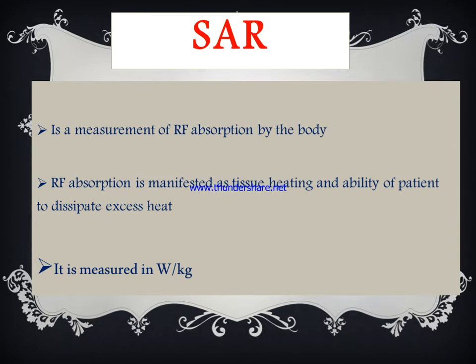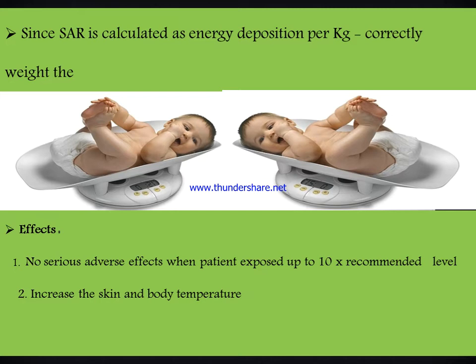SAR means specific absorption rate. SAR is the measurement of RF absorption by the body. RF absorption is manifested as tissue heating and the ability of the patient to dissipate excess heat. SAR value is measured in watt per kg. Since SAR is calculated as the energy deposition per kg, it correctly weights the effects. No serious adverse effect occurs when the patient is exposed up to 10 times the recommended level.